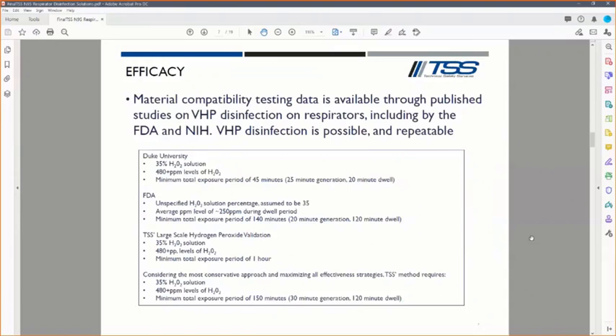And when I'm talking about a cycle, our disinfection process is a 35% hydrogen peroxide solution that's generated to at least 480 ppm or above. On average, our cycles are about 1,200 ppm for the duration, on average, of our generation and our dwell period. And this is based on the information that was available at the time of other EUAs that had been delivered, FDA studies, and TSS's decades of disinfection.